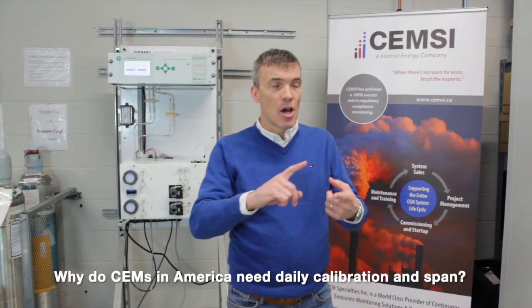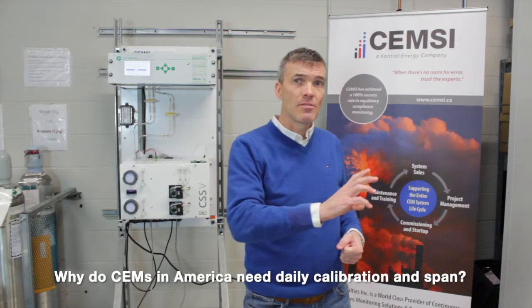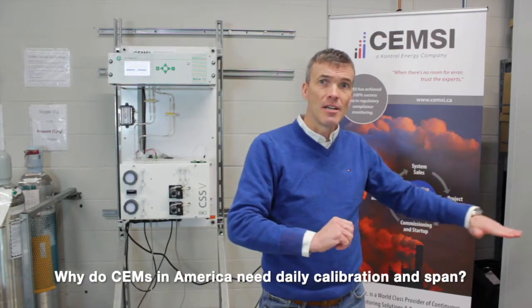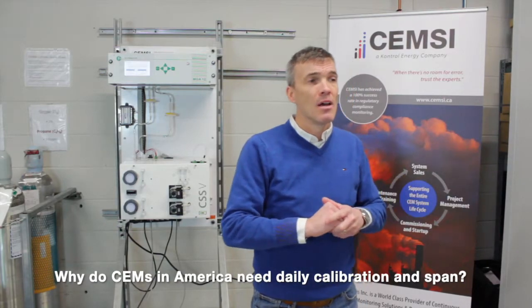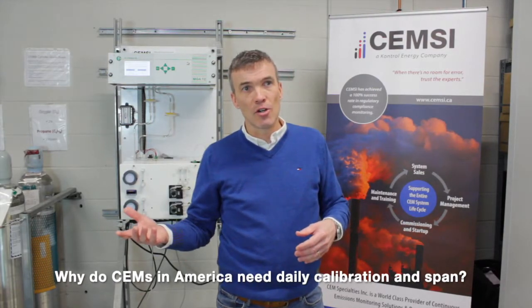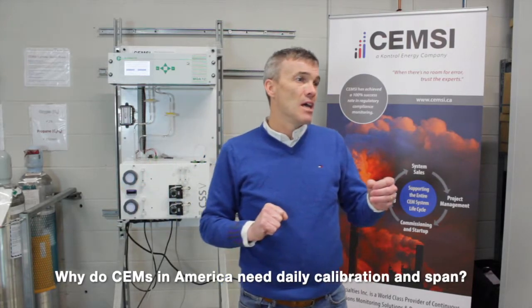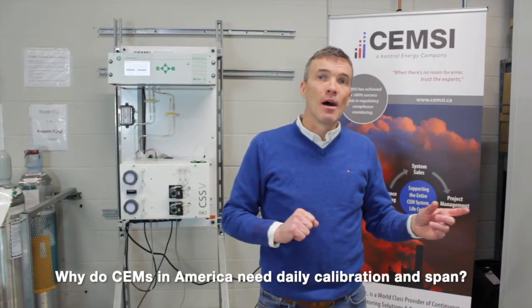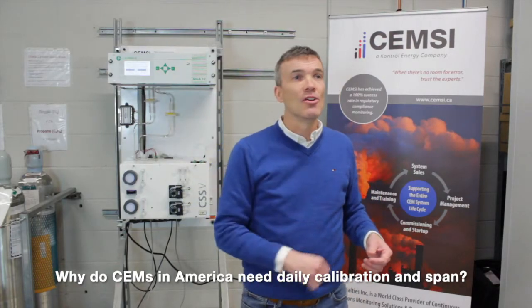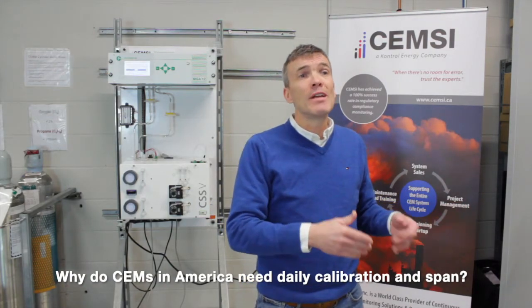But then the government's going to say, I need you to do a zero and span calibration every day, which means a zero gas, and some gas between 0 and 20% of full scale. You're going to inject it in and do a low reading. Then, and this is where it gets confusing, depending on the regulation you're in: if you're in Canada, you're going to pick a concentration between 80 to 100% of full scale value of the analyzer. If you're in the United States, Part 60, you're going to do 50% to 100% of the full scale reading. Part 75, you're going to do 80 to 100%. And you're injecting this span gas, and you're going to do it every day.